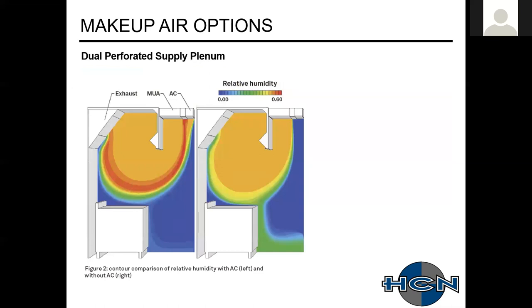On the right, both systems are working. Here you see it's coming in, here's the makeup air. That's creating, like I said, that air curtain effect, making sure that air doesn't diffuse into the space. Where the AC portion was shut off and it's just a standard makeup air plenum, you can see most of the air is getting sucked back in, but you're still going to have some diffusion in the space. And you can see that with the relative humidity contours here.